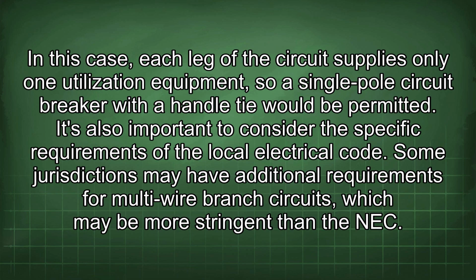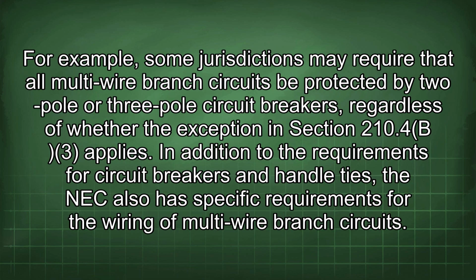It's also important to consider the specific requirements of the local electrical code. Some jurisdictions may have additional requirements for multi-wire branch circuits which may be more stringent than the NEC. For example, some jurisdictions may require that all multi-wire branch circuits be protected by 2-pole or 3-pole circuit breakers regardless of whether the exception in section 210.4(B)(3) applies.